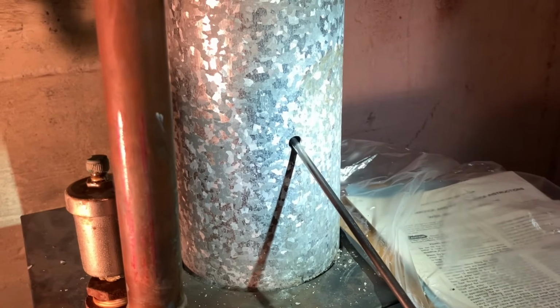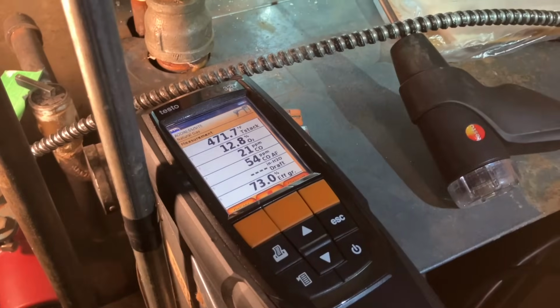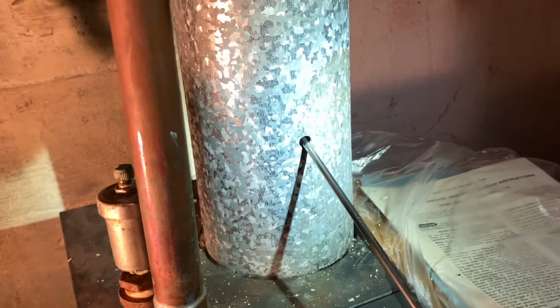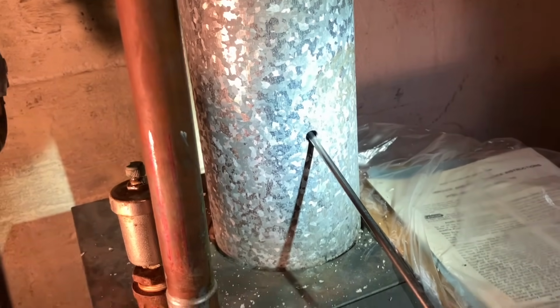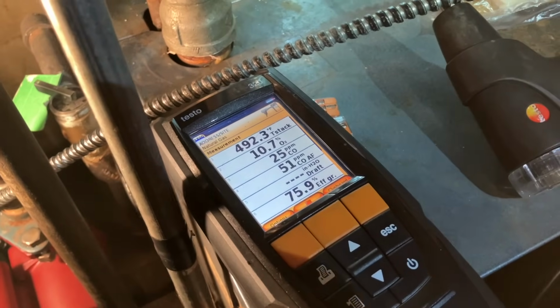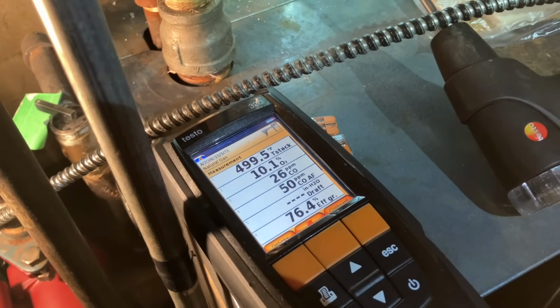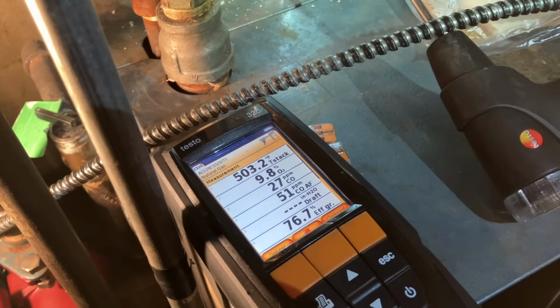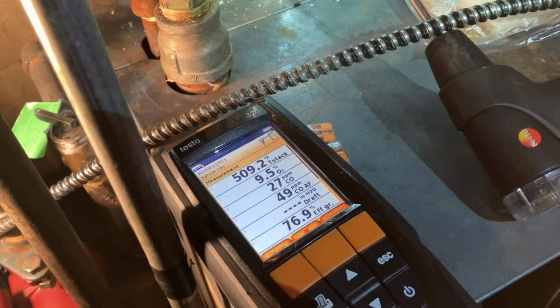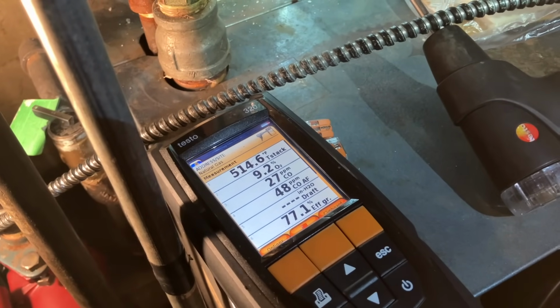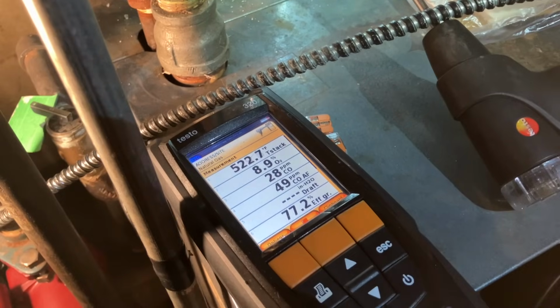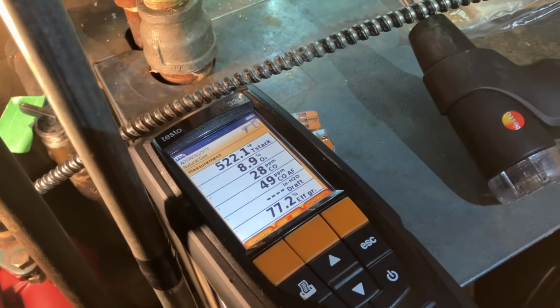Yes. All right, I drilled a hole approximately 6 inches off the top of the boiler between the boiler and the draft diverter. That is for our combustion analyzer, and the probe is halfway into the flue piping. Take a look at our numbers. We're almost at 500 degrees of stack temperature, and ideally it should be high 3s to low 4s of hundreds. O2 of 9.0 and dropping. Carbon monoxide, 28 parts per million.